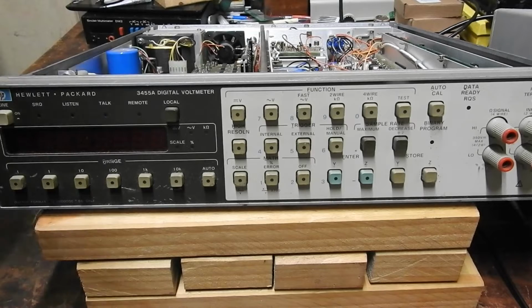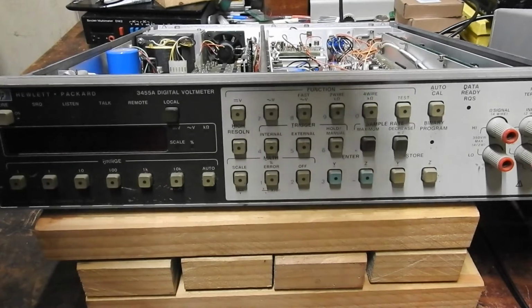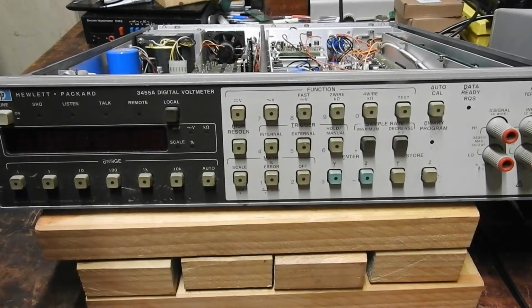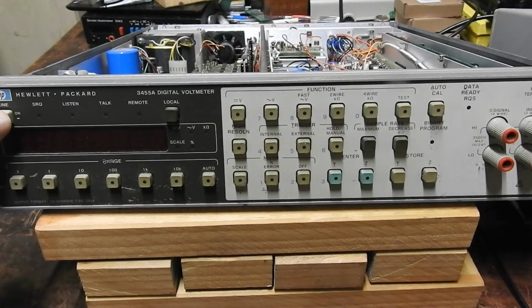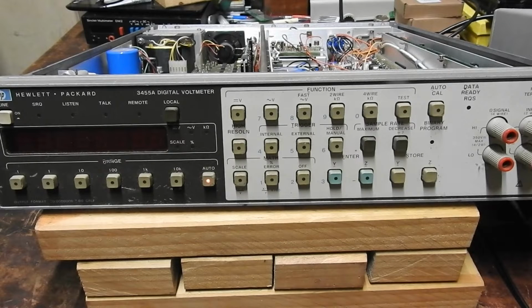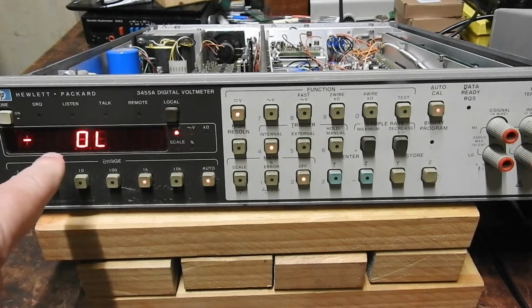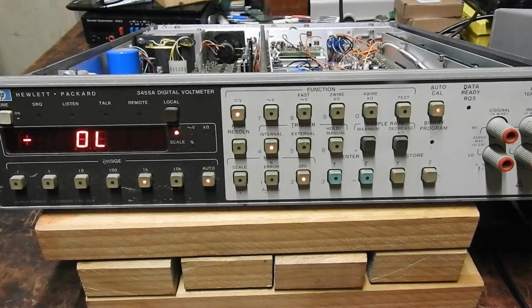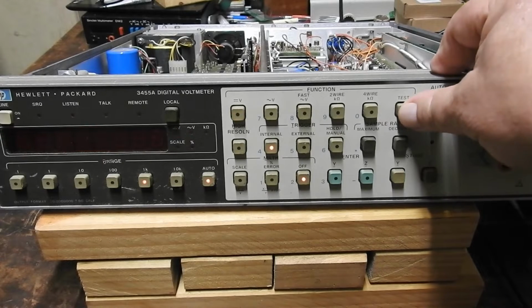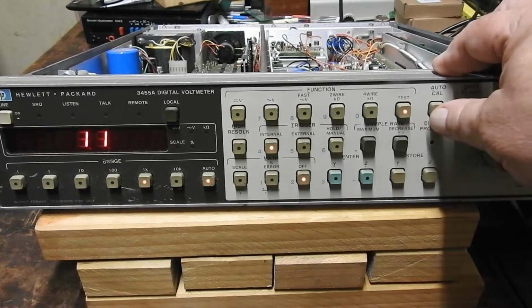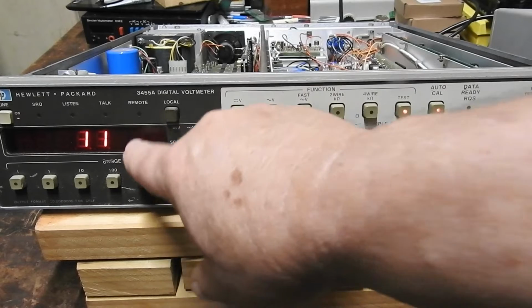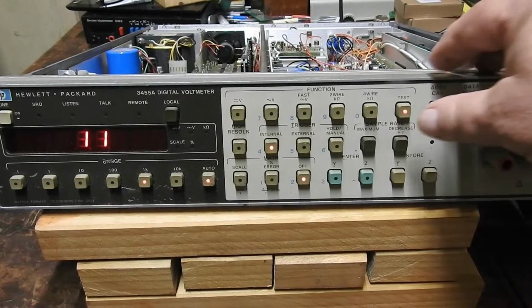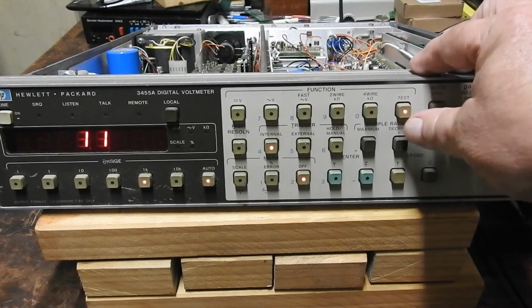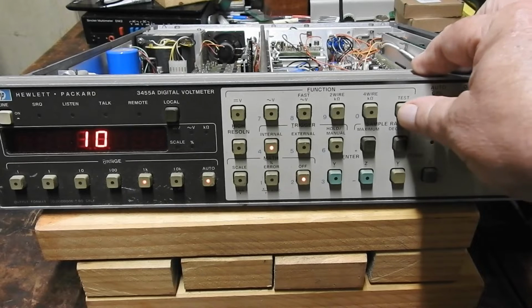Maybe all these are pretty good because none of them appeared bad with a multimeter, but I'm going to go over them with an oscilloscope this time. So we'll do that. The fault, if I turn it on, this has a fan that the other ones don't have. There's this overload coming on. And there's a test function which comes up with 11. It's testing auto cal constants. The manual's not very clear on it, but every time you press it, it counts down.